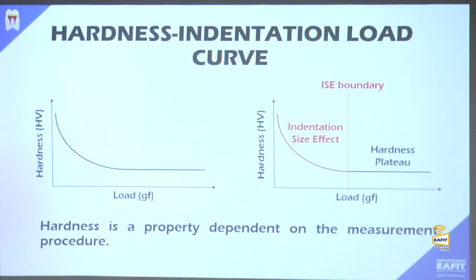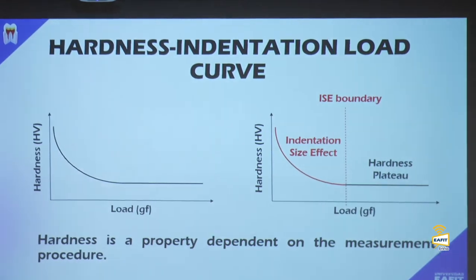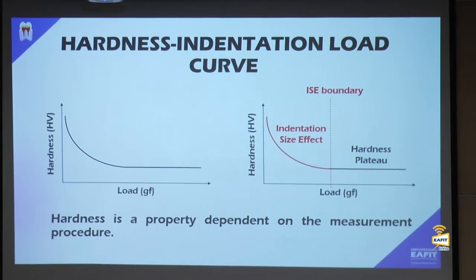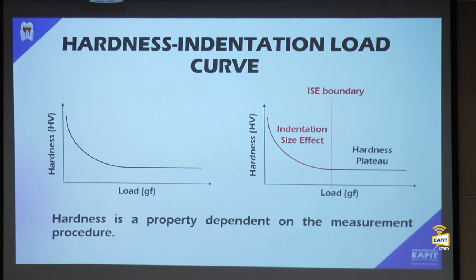To compare hardness values between materials, you must use the same load, same tip, and same dwell time — otherwise values are not comparable. The standard requires a full characterization across a range of loads: starting from small loads up to the maximum. For micro indentation, the maximum load is one kilogram and the minimum is 10 grams.